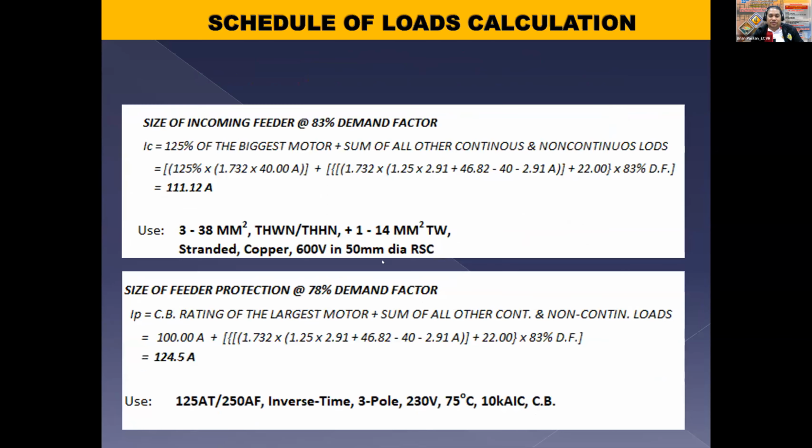Okay. So, again, kasi si motor load is nasa highest phase current, kaya nga deduct ako ng 40 dito para hindi madoble siya. Kasi nandoon siya sa highest phase current sa 46. If wala siya doon sa highest phase current, then hindi ito i-deduct ko ng 40. May instances kasi na si highest current natin motor load is wala doon sa highest phase current din. So ito yung circumstance na ito. Okay.